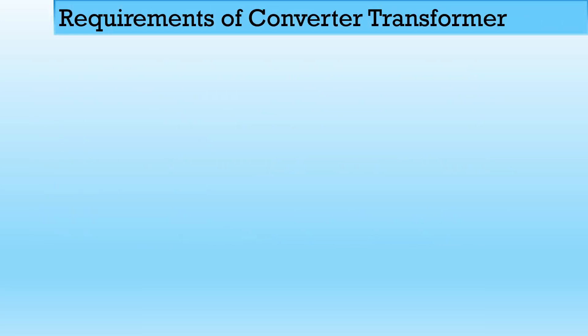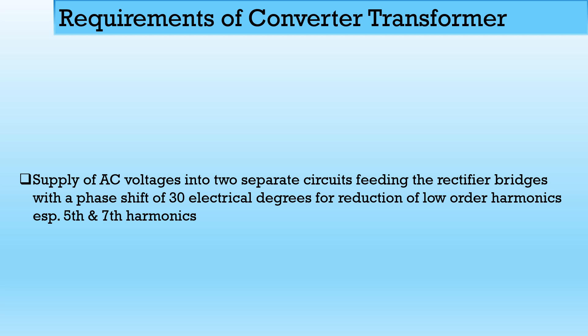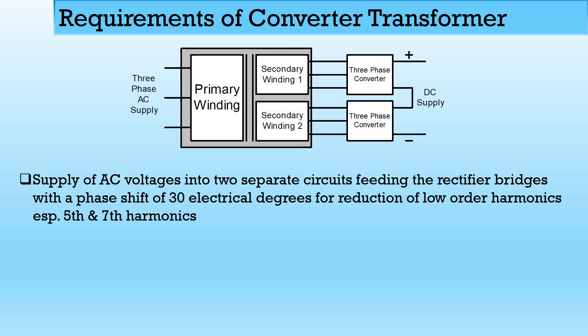Let's begin with the requirements of the Converter Transformers. The first requirement is supply of AC voltage into two separate circuits, feeding the rectifier bridge with a phase shift of 30 degrees electrical, for reduction of lower order harmonics — especially the 5th and 7th harmonics. The secondary winding is divided into two parts, and the EMF induced in the first part has a 0-degree phase shift with the primary winding.